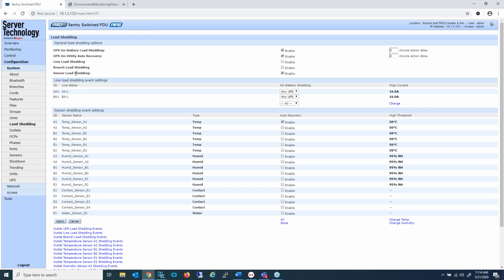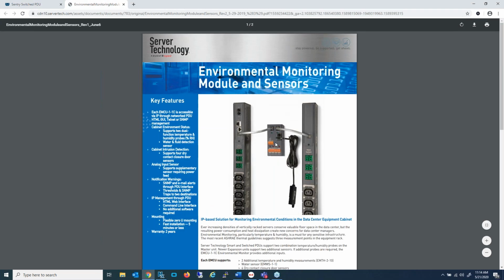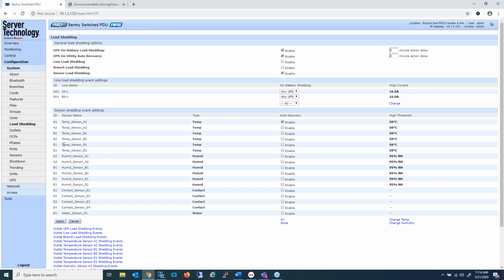Finally, we have sensor load shedding, which I have already enabled. Sensor load shedding refers to temperature and humidity sensors that are attached to the master PDU and the link PDU. The master PDU supports 2 combination temperature and relative humidity sensors, and the link unit supports an additional 2. We see quite a bit more than 2 in this case, because this system actually contains what we call an EMCU, or an environmental monitoring control unit. That's this device that is located between the master PDU and the link PDU. And that device adds the ability for an additional 2 temperature and humidity sensors. So we see that as the E1 and E2 for temperature, and we see E1 and E2 for humidity.